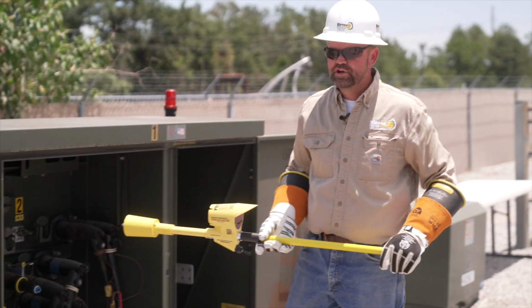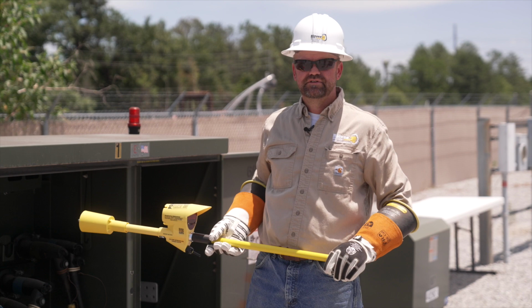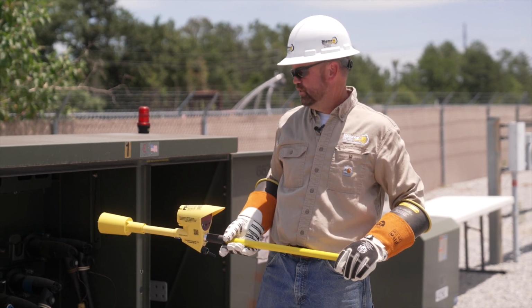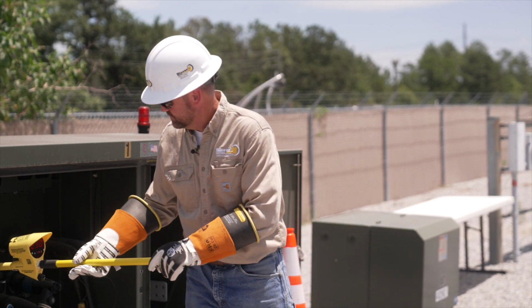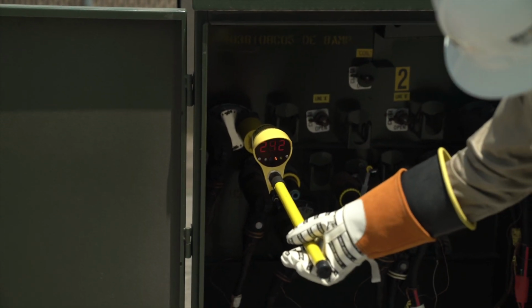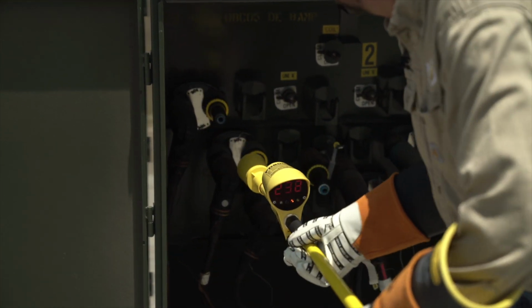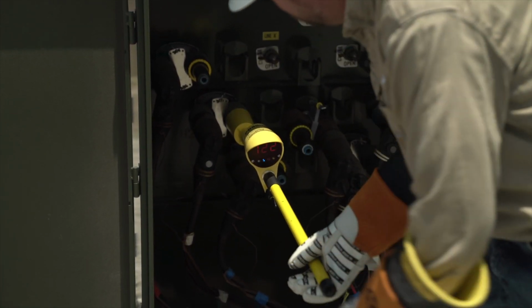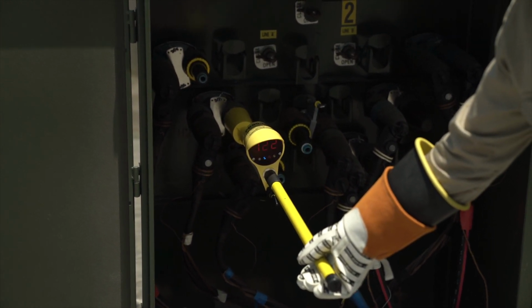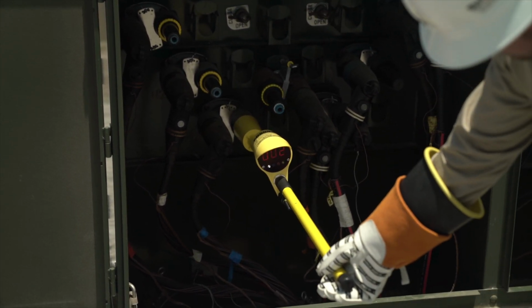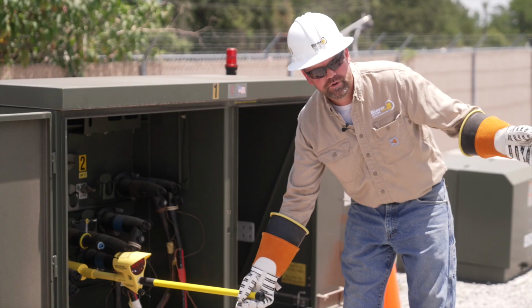But let's just say I started with the top bushing. Again, I had no nomenclature, no colors, no markings whatsoever. I have my red light near 240 degrees. So that is in fact not in phase. My H2A bushing, I have near 120 degrees, my blue light, so that is also not in fact in phase with that bushing. So my H3A bushing is the phase that is in fact feeding where my reference probe is inserted into that primary bushing.